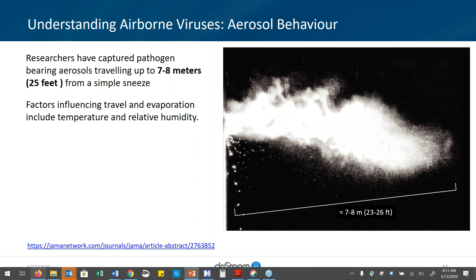Droplets are by definition larger than 20 microns, and whilst the small droplets and aerosols can be from 10 to 20 microns, we're generally concerned about those that are below 10 microns. We have droplet nuclei that can be as small as 0.5 microns. In a low ambient RH environment, the small droplets and aerosols may immediately shed moisture and reduce size and weight to become a droplet nuclei. The droplet size impacts its float time, ability to travel, and its depth of penetration into the respiratory system.